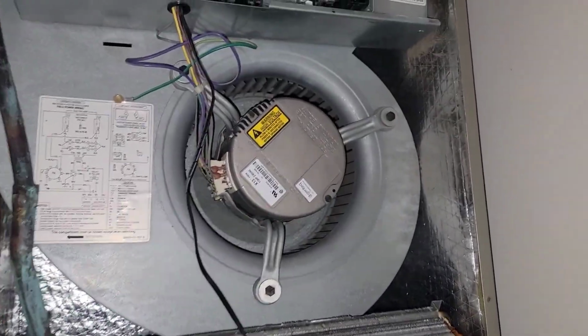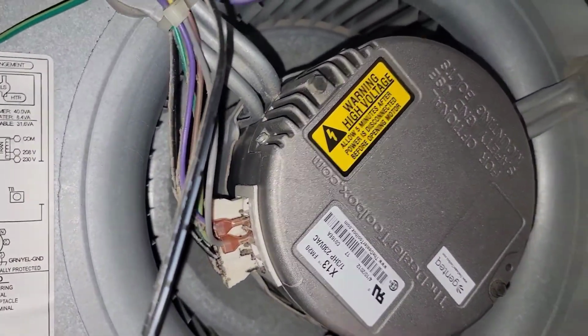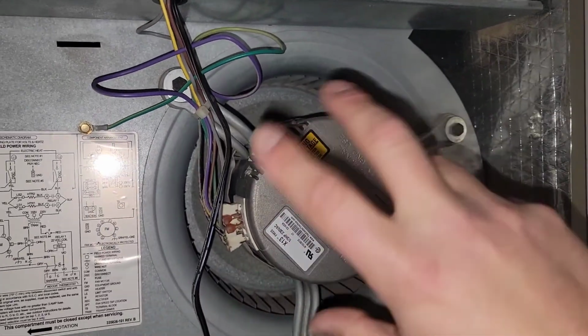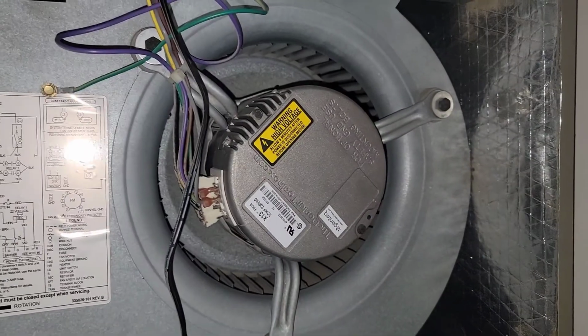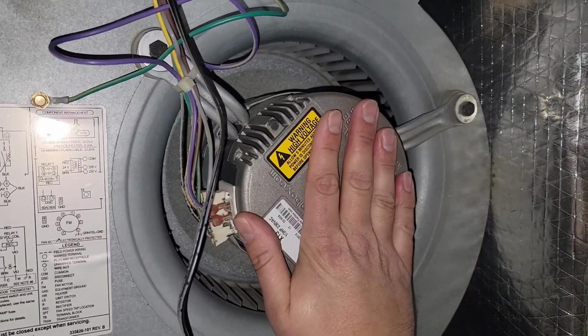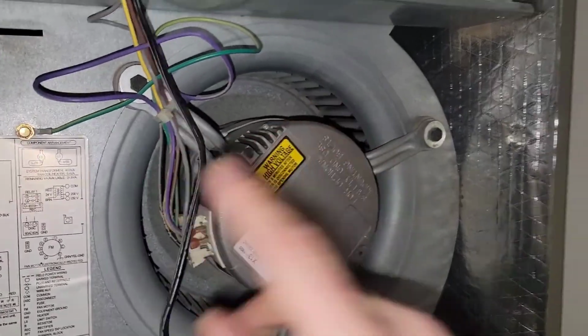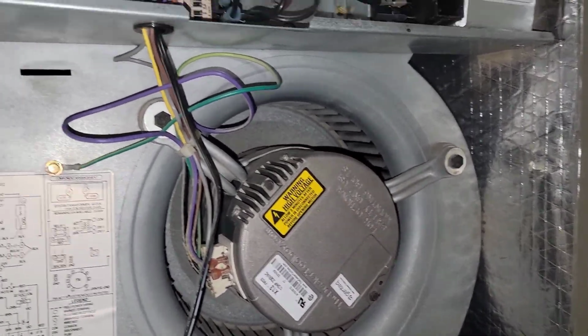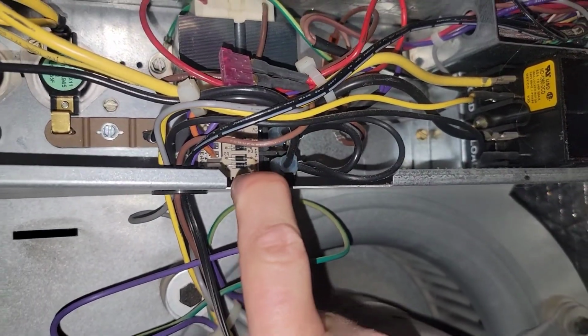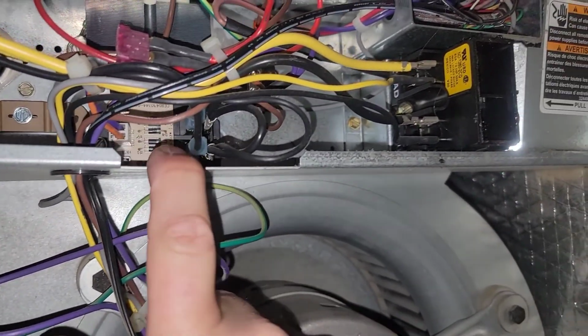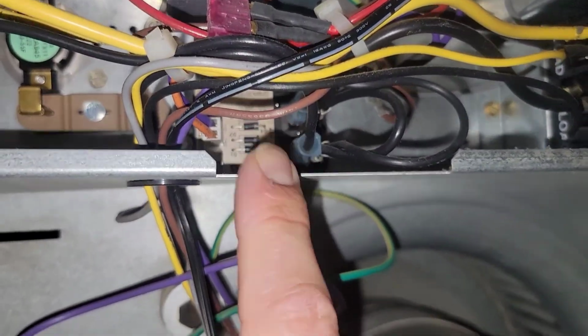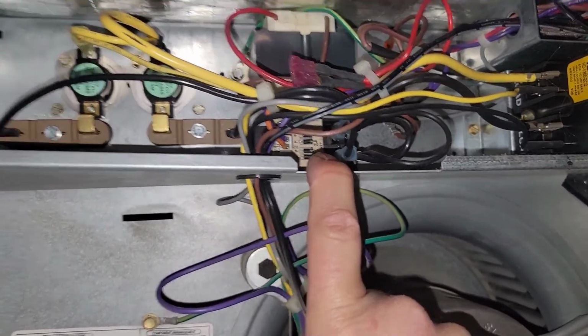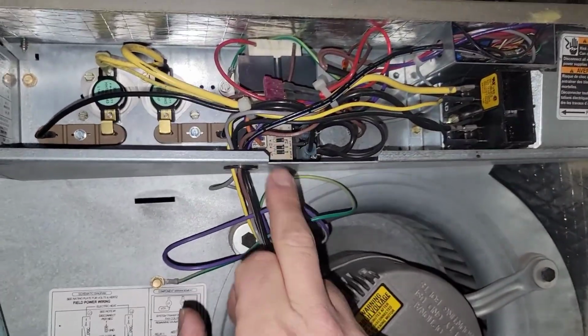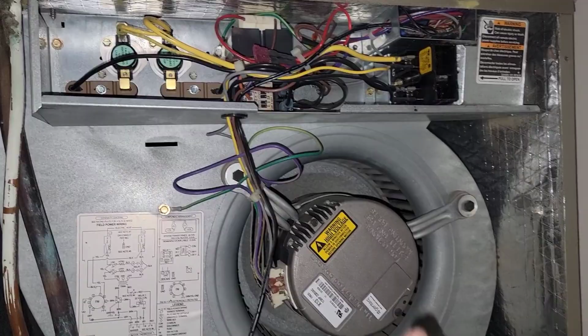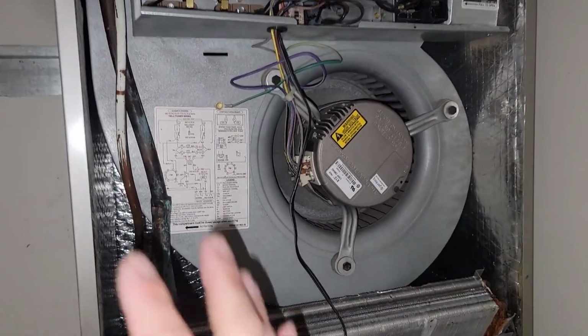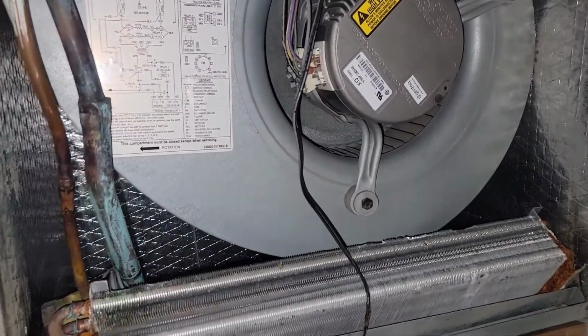Okay. So we got an X13 motor. And these go bad. Sometimes they'll go back and forth. That's how you know they're bad. Sometimes they won't run and they have power. And sometimes they'll run all the time. Sometimes this relay right here will go bad. And this relay not only controls the heaters, but it controls the motor as well. Some of these apartments have sequencers, some of them have relays like this, and that sequencer will go bad. You'll have the unit in the cooling mode, but the indoor fan won't be running, and that'll cause the indoor coil here to freeze up.